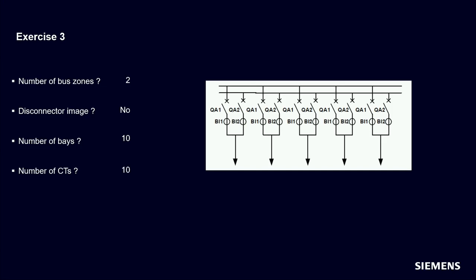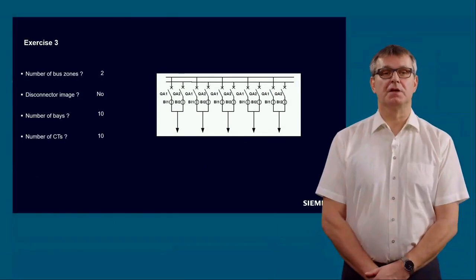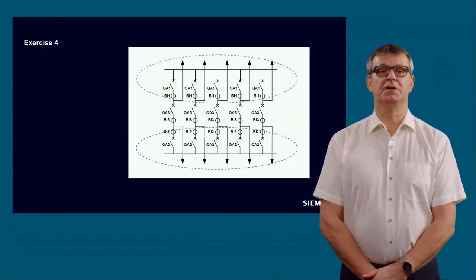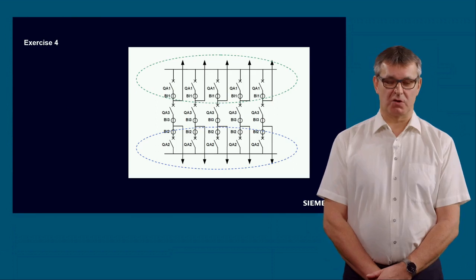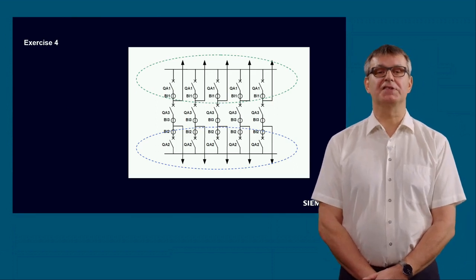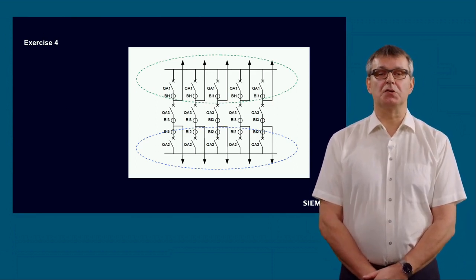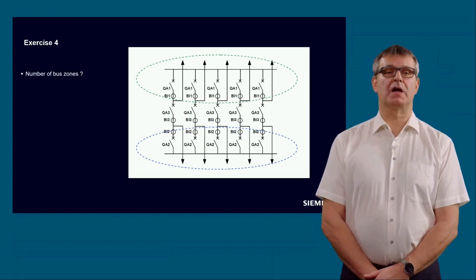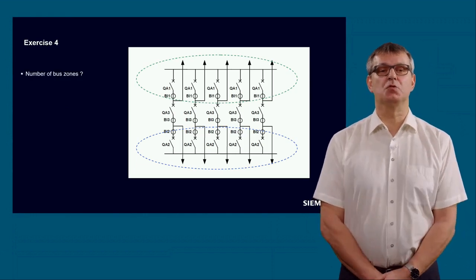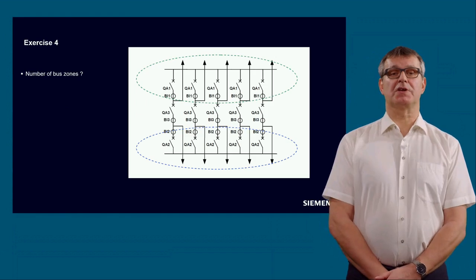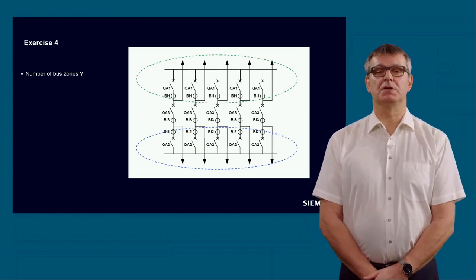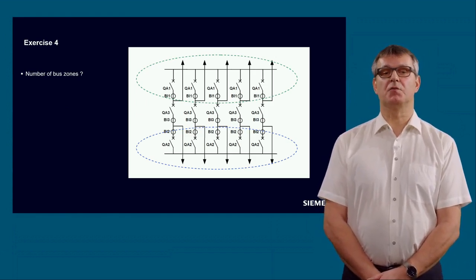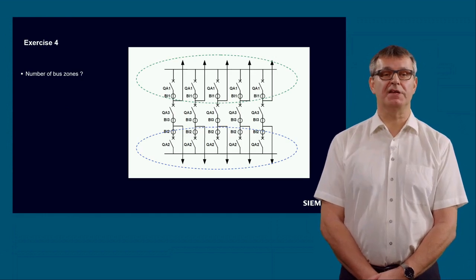Number of CTs, okay, that's easy. These are 10 current transformers, 10 measuring points. Last exercise: that's a so-called circuit breaker and a half scheme. Maybe also interesting to look at. How many bus zones do we need in a circuit breaker and a half scheme? So that's a circuit breaker and a half scheme with so-called 5 diameters.